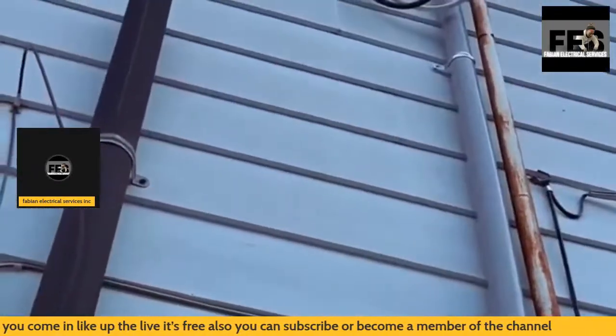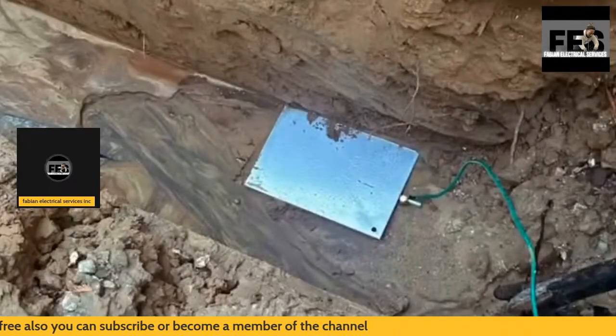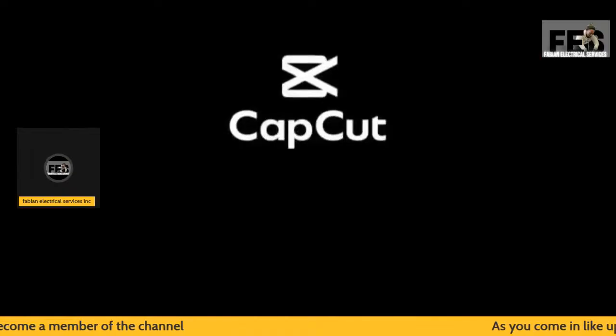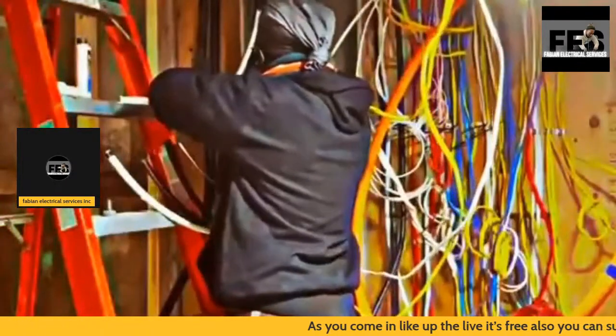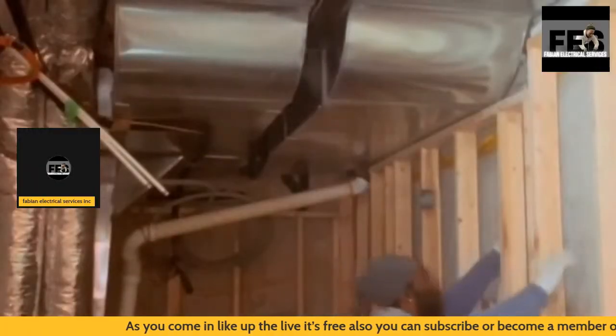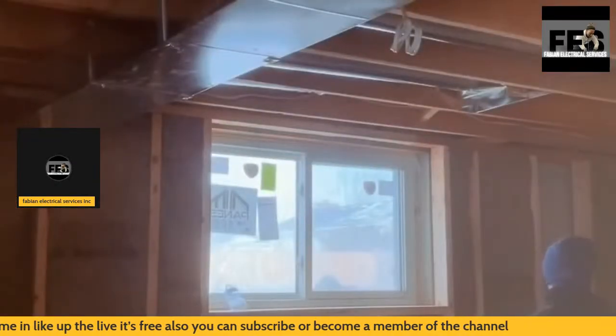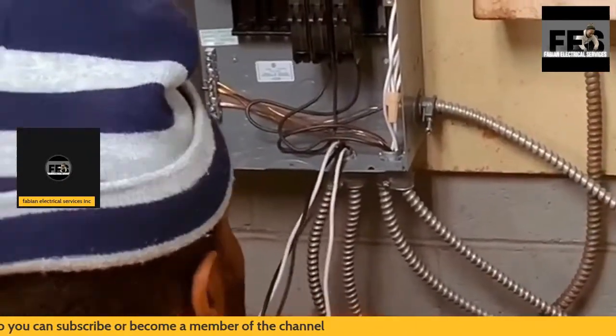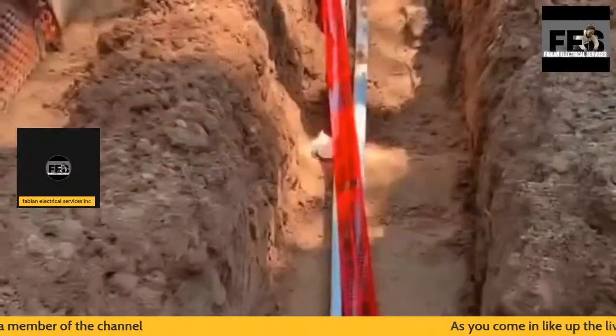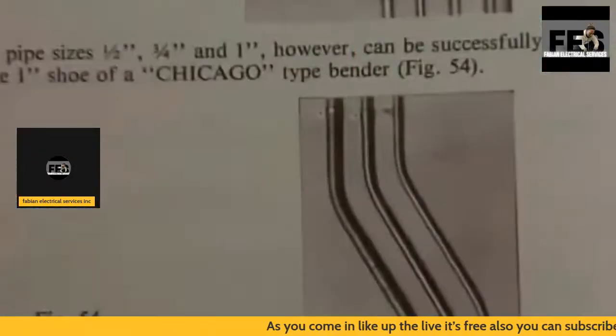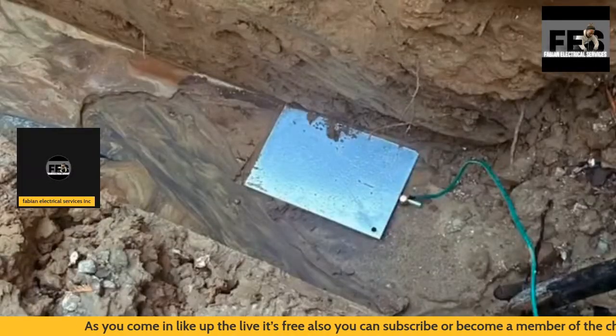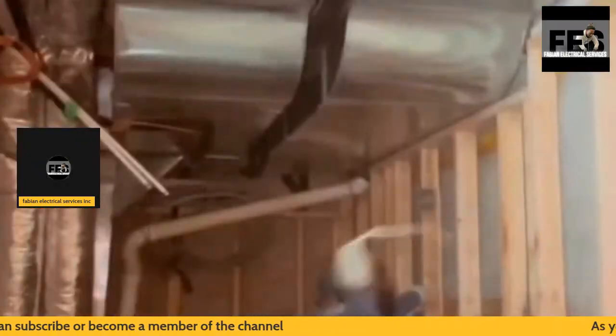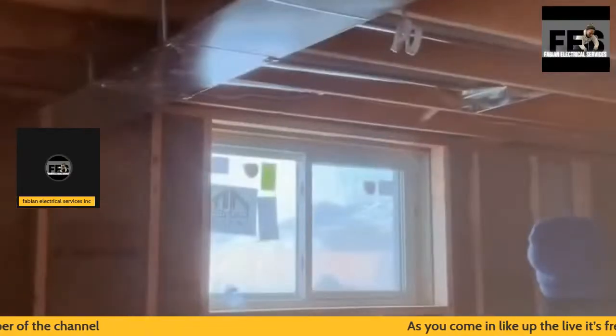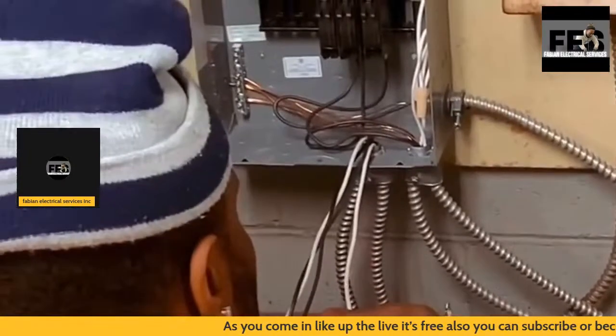A 400 amp disconnect, fusible, installed inside the main home in the basement. This disconnect is required because of the rule staying within 5 feet of the disconnect, which is the main electrical disconnect located outside at the main electrical meter base. The meter base outside has to have a disconnect between the panel and the meter base. For this reason, I have a 400 amp disconnect installed.